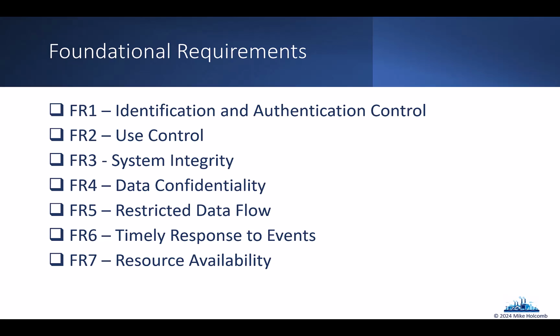You can see FR6. How quickly can we respond to incidents? And part of that is, how quickly can we restore functionality? What if just a PLC goes down? What if it just shorts out for some bizarre, strange reason? Do we have a spare sitting there? Can we restore a backup of the ladder logic to that PLC? How long does that take? 30 minutes, 30 days, hopefully a lot less.